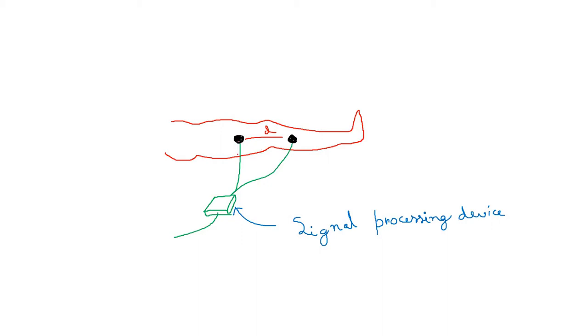So what will happen? Then we flow small amount of AC current through these two electrodes. And you know human body is conductive. So the blood flowing through different veins or arteries will conduct the electricity. From this electrode, if the small amount of AC current enters, this current will come out. And here this is signal processing device or signal conditioning circuit which will measure the resistance of the part of the body.